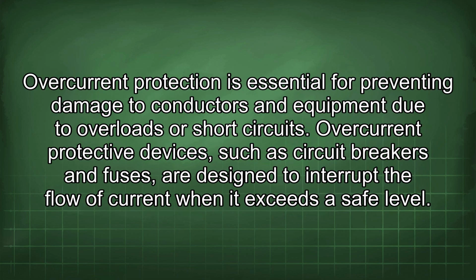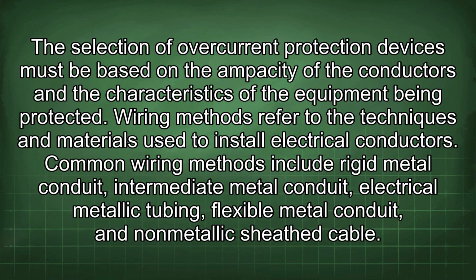Overcurrent protection is essential for preventing damage to conductors and equipment due to overloads or short circuits. Overcurrent protective devices such as circuit breakers and fuses are designed to interrupt the flow of current when it exceeds a safe level. The selection of overcurrent protection devices must be based on the ampacity of the conductors and the characteristics of the equipment being protected.